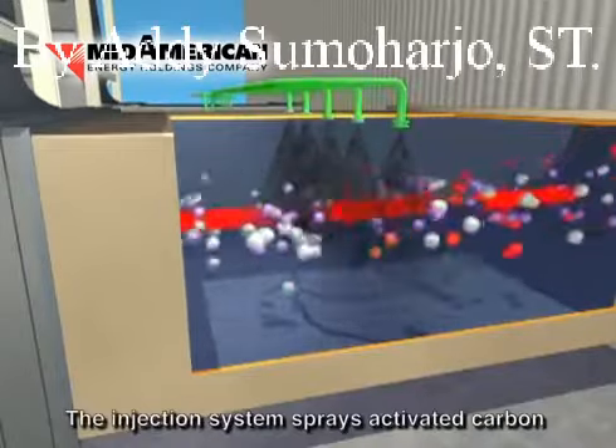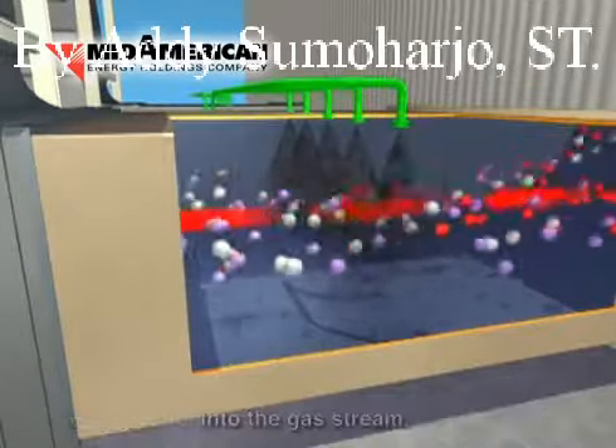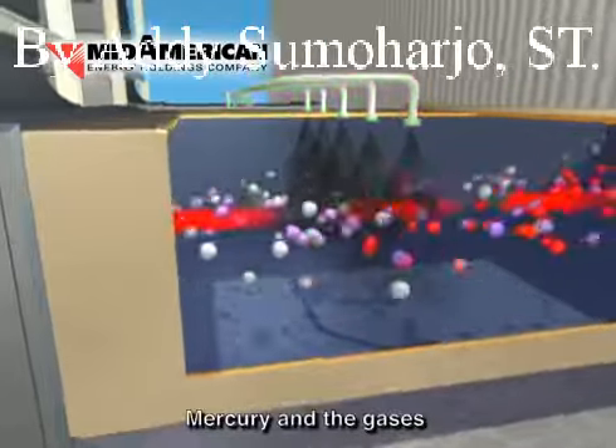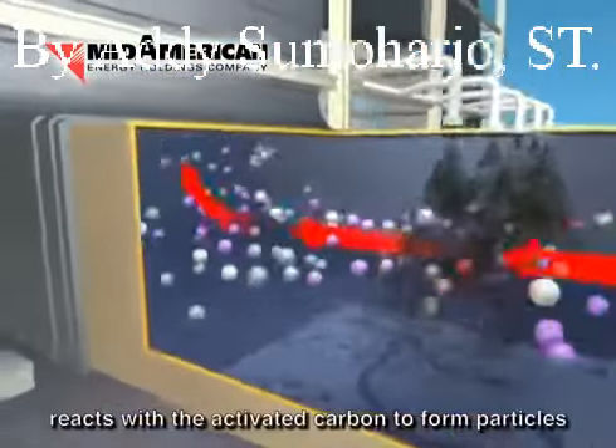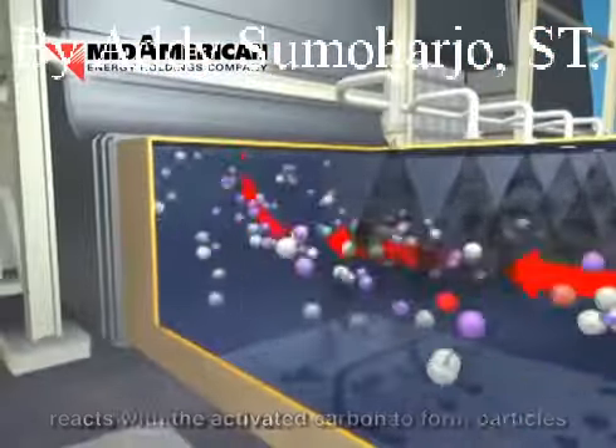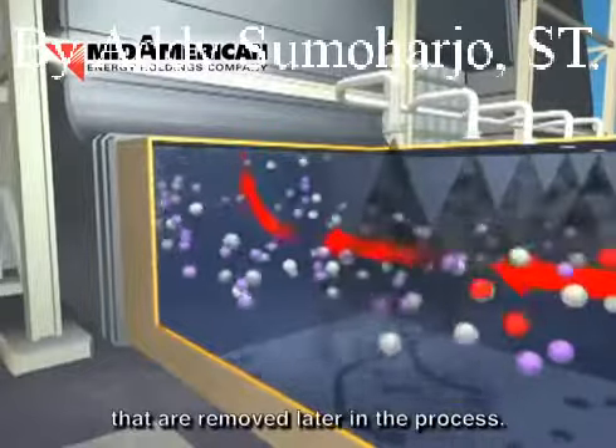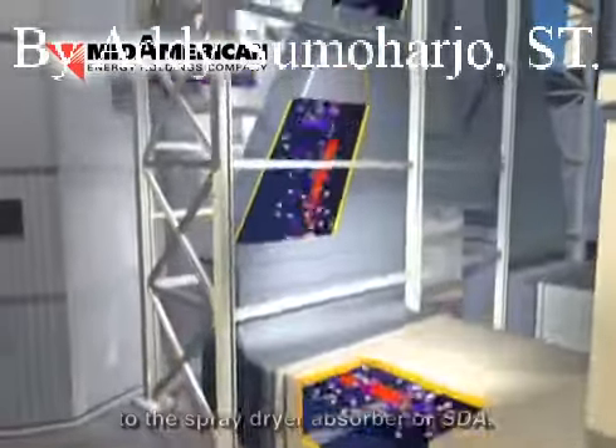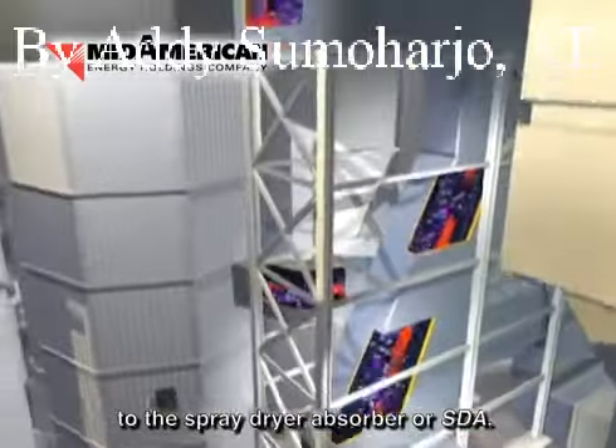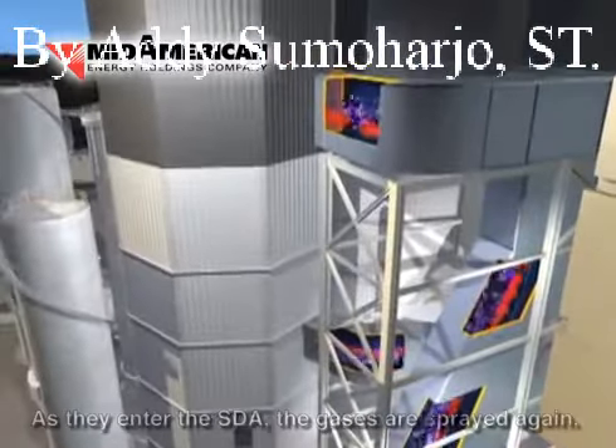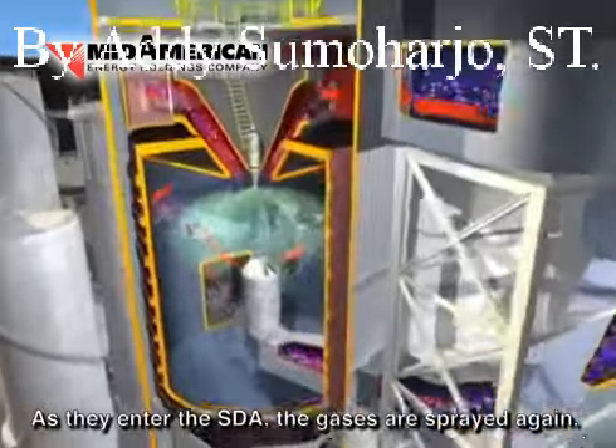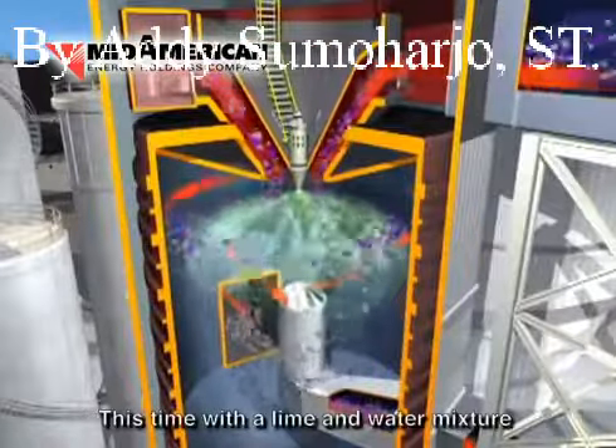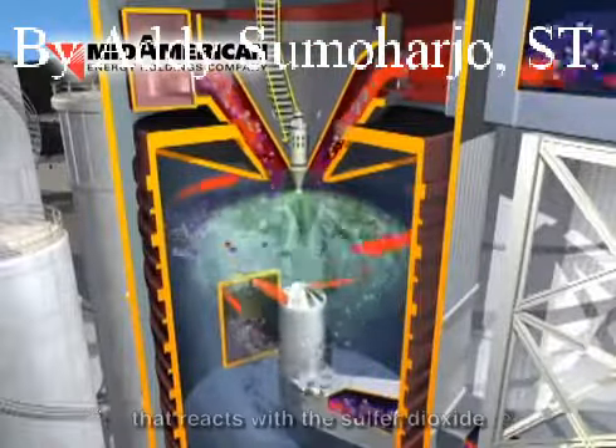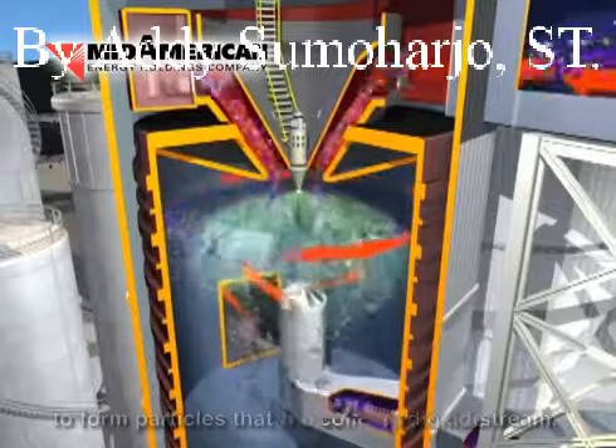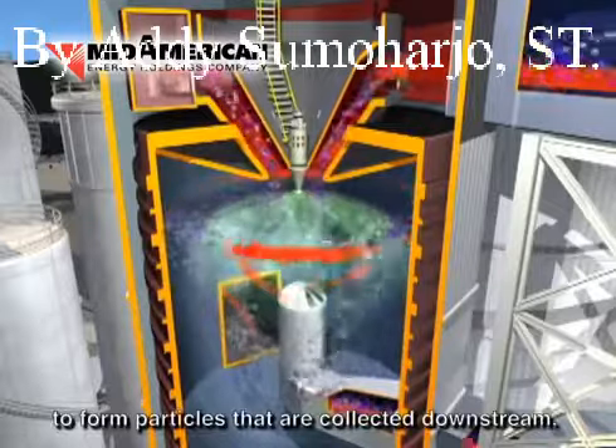The injection system sprays activated carbon into the gas stream. Mercury in the gases reacts with the activated carbon to form particles that are removed later in the process. The gases continue on to the spray dryer absorber, or SDA. As they enter the SDA, the gases are sprayed again, this time with a lime and water mixture that reacts with the sulfur dioxide to form particles that are collected downstream.